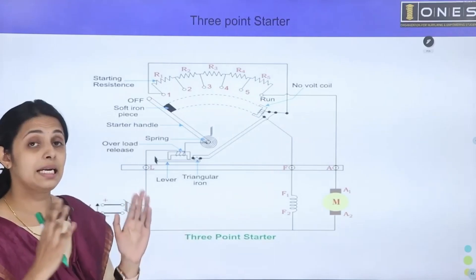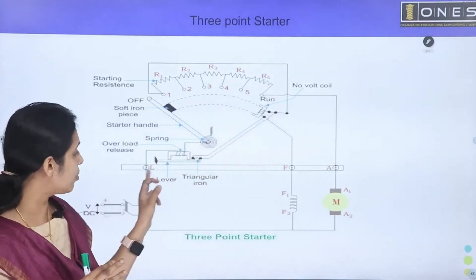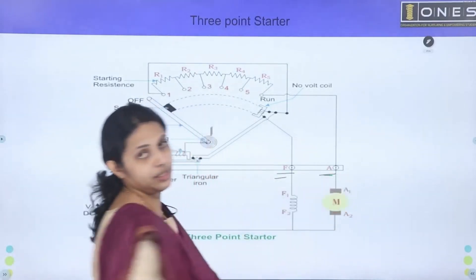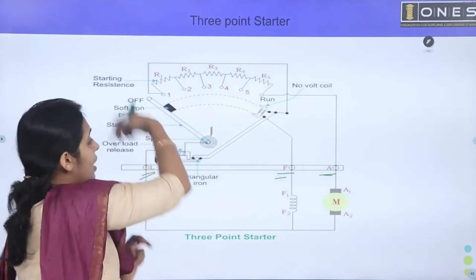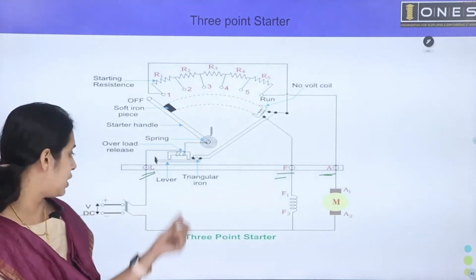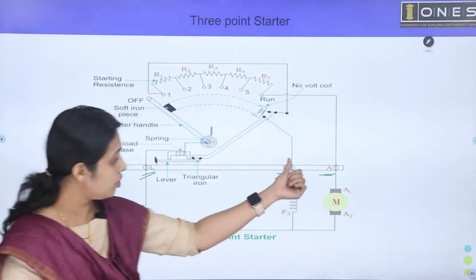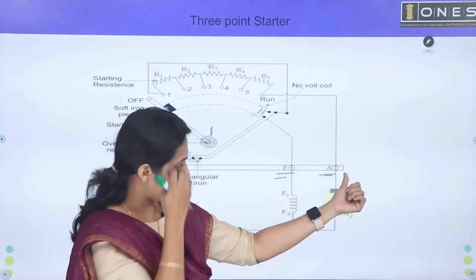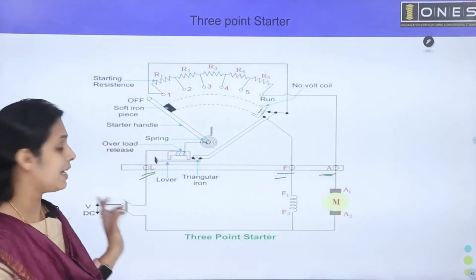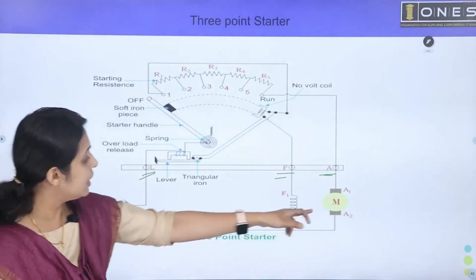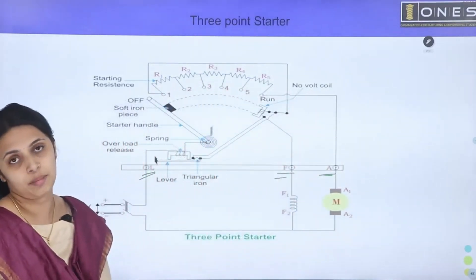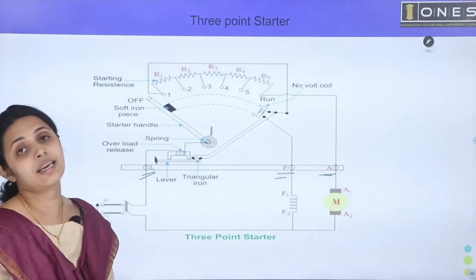The 3-point starter has three terminals: Line Terminal (positive supply), Field Terminal (motor field winding), and Armature Terminal. A series resistance is connected to the armature to limit starting current. The armature current becomes Ia = V / (Ra + external resistance), reducing the initial current significantly.